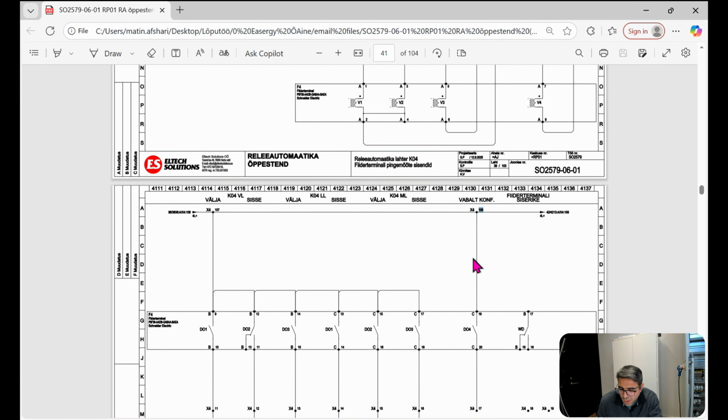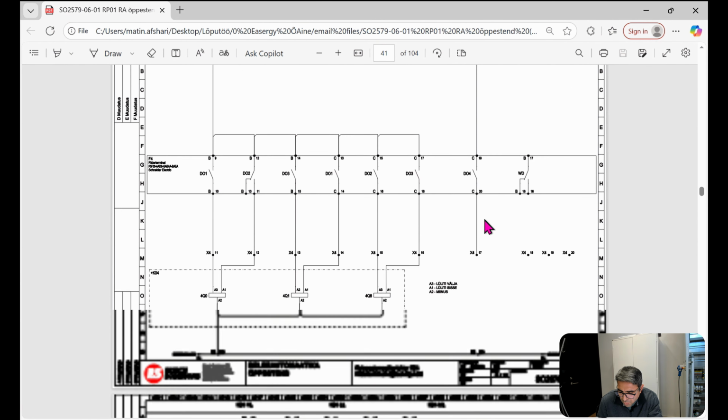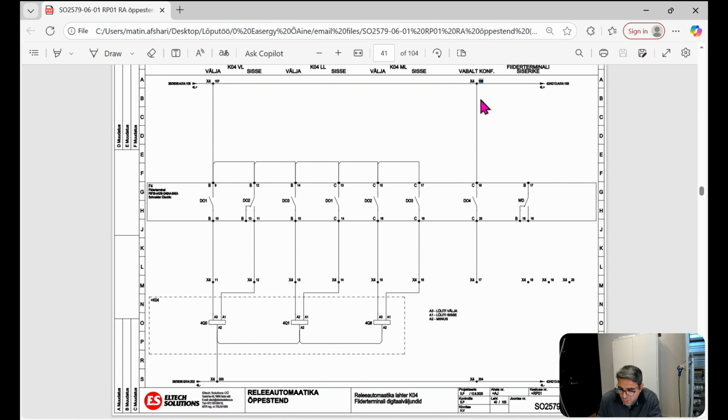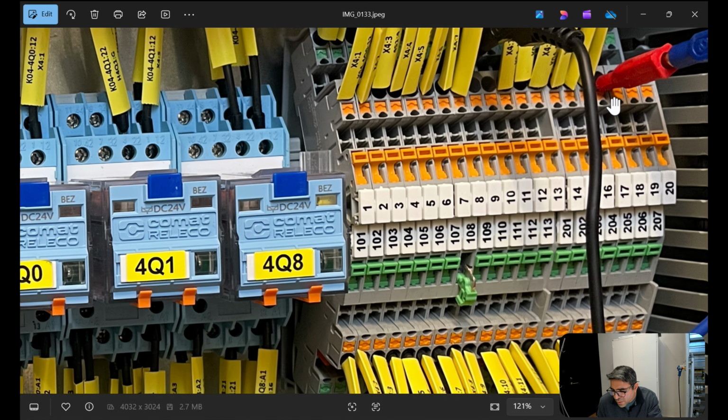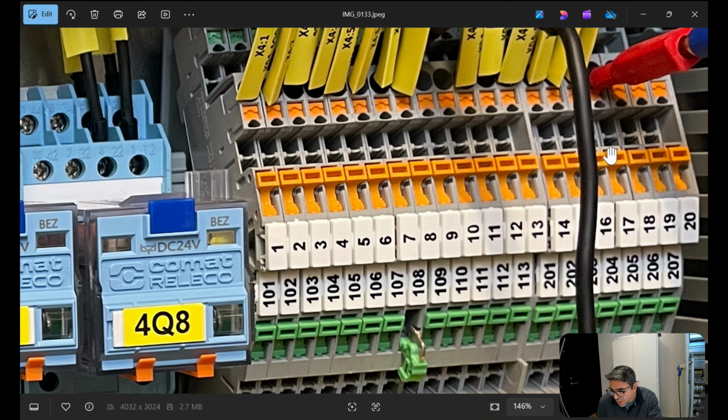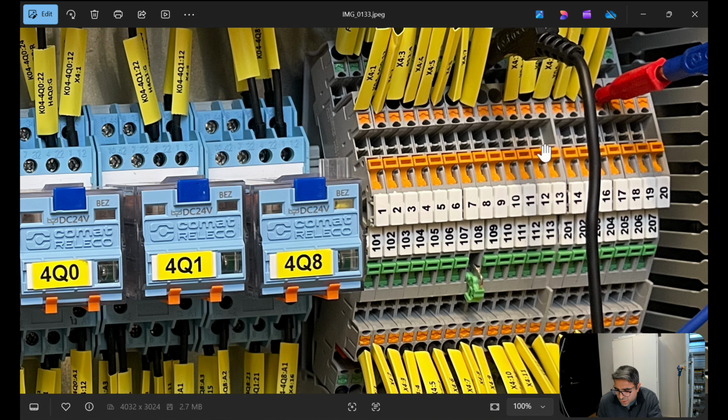The 108, it's already connected to the plus, so we have to disconnect it. On the terminal, we have the possibility. So remember terminal 17, terminal 108. Let's go back to the picture. Terminal 17 is this one, and you see this is the cable that we have connected, and this is connected to the minus in the feedback of the tester device. So 17 is simple. It was free. It's connected to here. But 108...